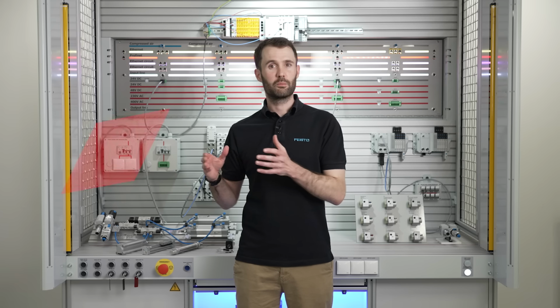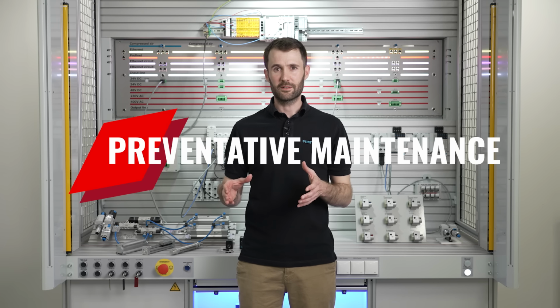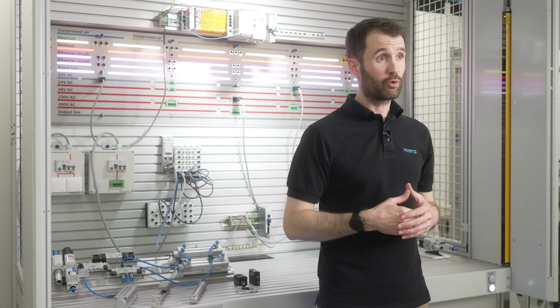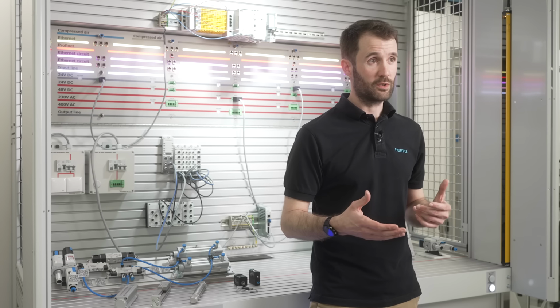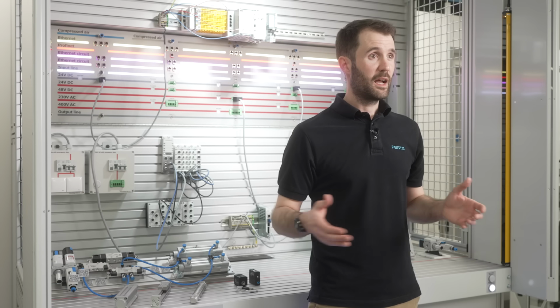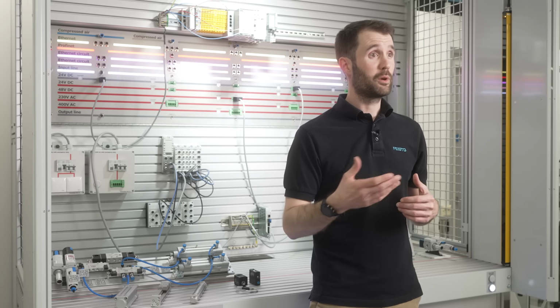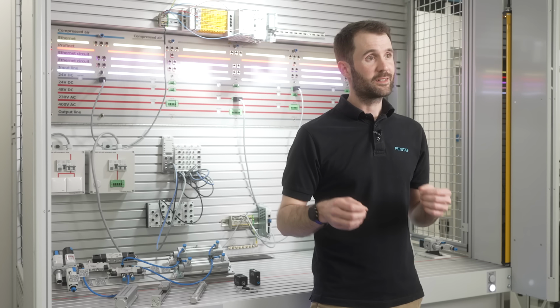So now let's step into preventative maintenance. And preventative maintenance is just how it sounds. It's trying to prevent any reactive maintenance. So with preventative maintenance, let's take a production line in this case. The actual OEM who created the production line will typically give the end user a maintenance schedule. And this could be every 2 to 3 months or a couple of weeks, a schedule and standard maintenance activities which should be performed. All equipment suppliers that provide equipment into that production line will also have guide maintenance for stuff like lubrication to be applied into the piston rod or cleaning down any, say, guides.